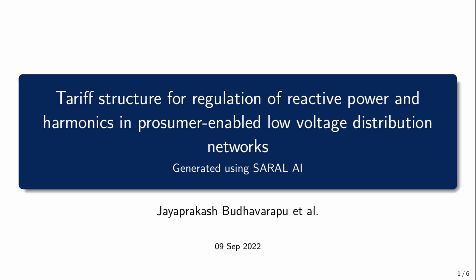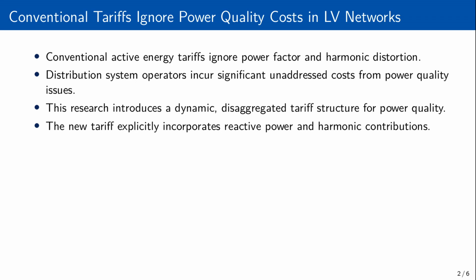Let's begin by understanding the problem this research addresses. Conventional active energy tariffs in low voltage distribution networks do not account for critical power quality parameters such as power factor and harmonic distortion. This oversight results in significant unaddressed costs for distribution system operators and provides no economic incentive for consumers or prosumers to improve their power quality profiles.